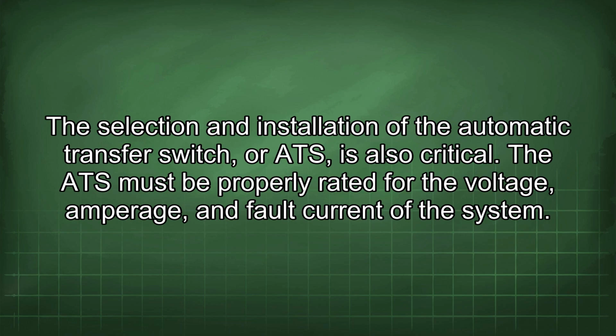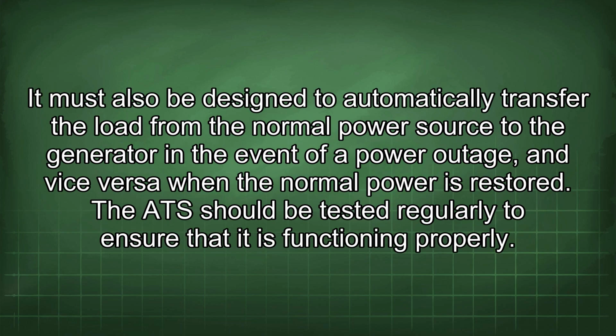The selection and installation of the automatic transfer switch, or ATS, is also critical. The ATS must be properly rated for the voltage, amperage, and fault current of the system. It must also be designed to automatically transfer the load from the normal power source to the generator in the event of a power outage, and vice versa when the normal power is restored. The ATS should be tested regularly to ensure that it is functioning properly.